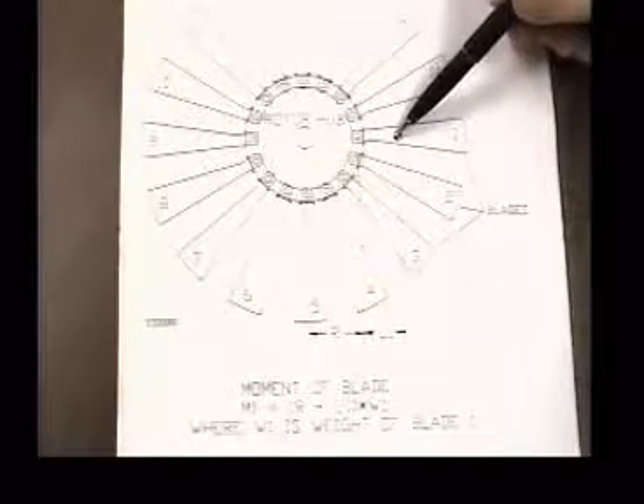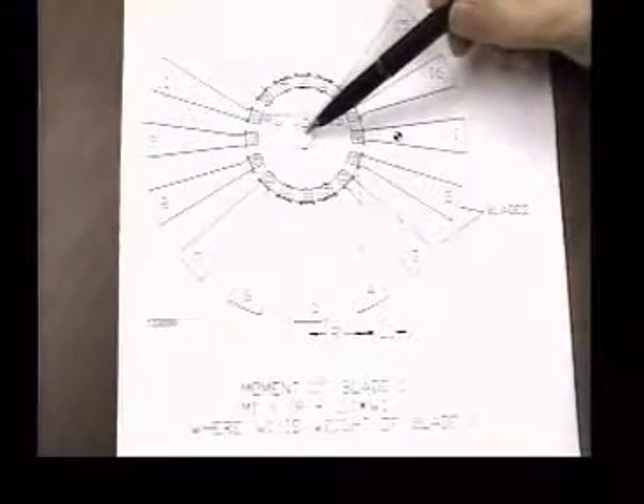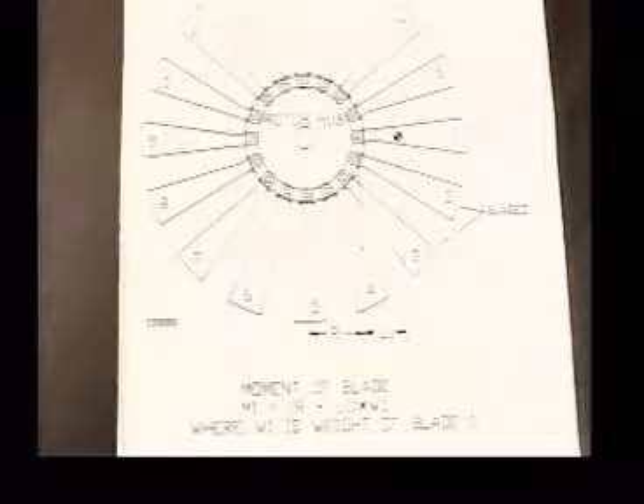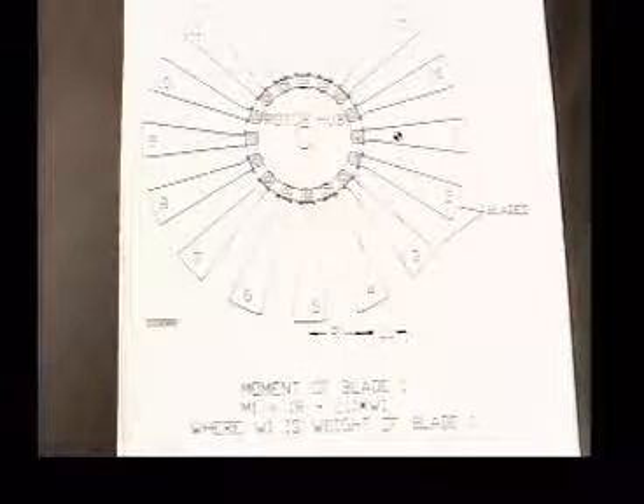to the weight of the blade times the distance between the center of gravity and the center of rotation of the blade. This quantity is a measure of the static unbalance of the blade, and it relates to the amount of unbalanced force that will occur when the blade spins at its speed, which might be as high as 9,000 RPM. By measuring all the blades in the set initially and then sorting the blades in the most desirable order, it's possible to match blades so that blades of equal static moment are placed opposite each other and counteract each other in terms of unbalanced moment. More sophisticated programs are available that also compensate for the rotor hub unbalance.